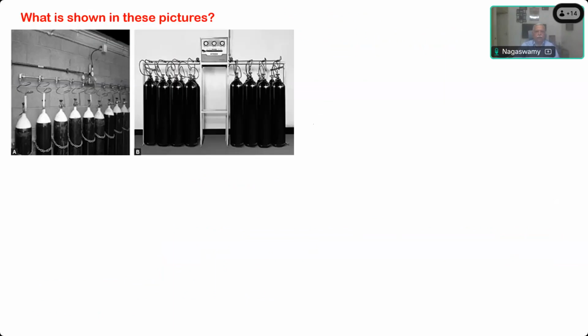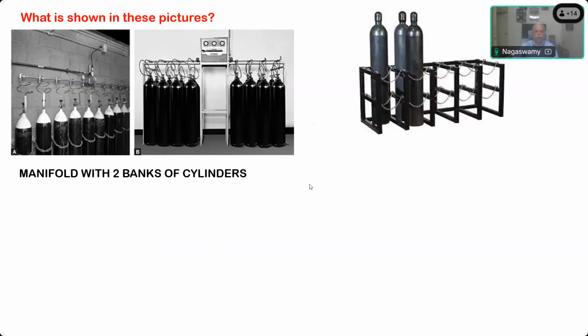Now, what is shown in these pictures? Cylinder manifold. Okay, so a manifold with two banks of cylinders. In the B picture, you are seeing one bank here and this is another bank. So this is a manifold room with two banks of cylinders. What is this? Gas storage. This is the correct method of storing the gases. Portable gas cylinders should not be made to lie horizontally on the floor. They should always be kept vertical with individual support.